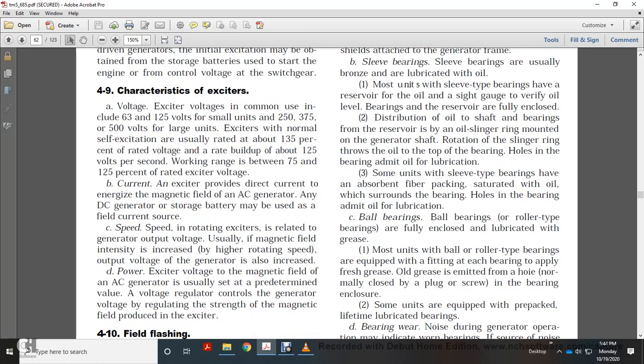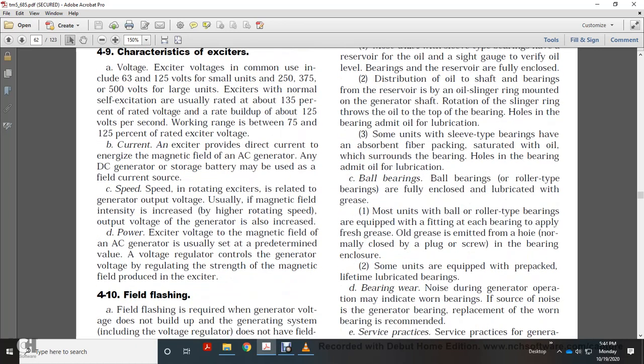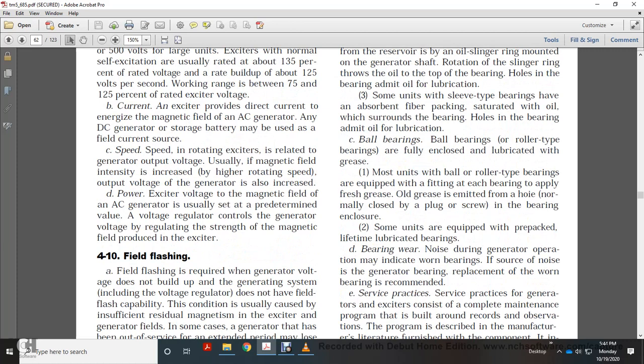The ball bearings are roller type bearings that are fully enclosed, lubricated with grease. Most units of the ball bearing roller type are equipped with a fitting for each bearing, applied with fresh grease, with the hole normally closed by a plug or screw within the bearing enclosure. Some units are equipped with a pre-packed lifetime lubricated bearing.